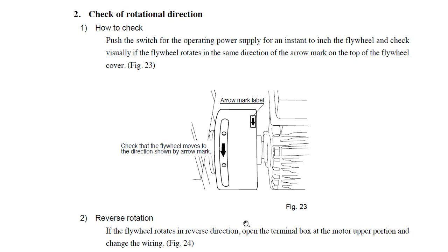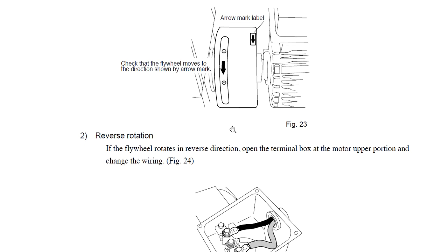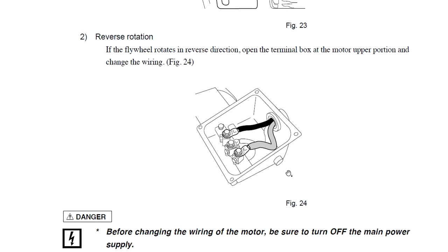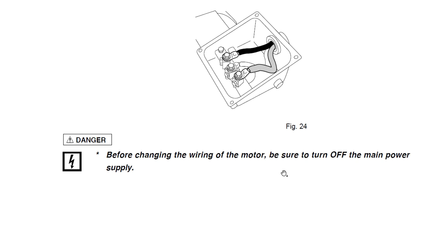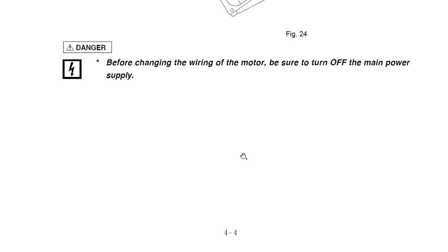Don't forget, before you start your equipment, to have all the valves open to make your equipment ready. If you have a reverse rotation, you should check your connection of the terminal box here and change the wiring. But we have a message here: before changing the wiring, switch off the power supply, the main power supply.